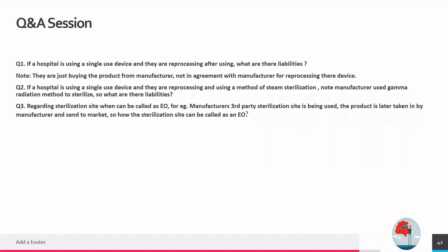First, they have to prove to the competent authorities and the notified bodies, with a whole QMS system in place, for reprocessing and repackaging or whatever process they are doing in a new way. Though the intended purpose was the same, the method was different. Because if anything happens, the original manufacturer should not be blamed, because they don't have an agreement with you. So they become an independent manufacturer themselves because the method of sterilization was different.